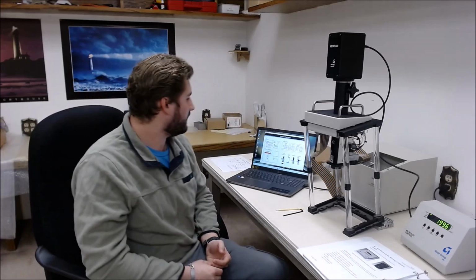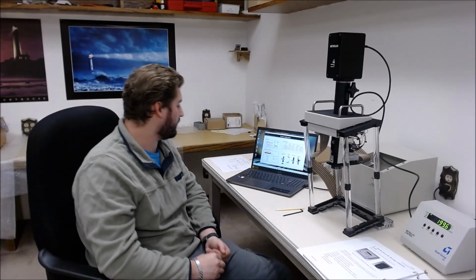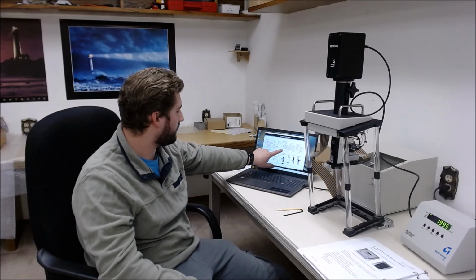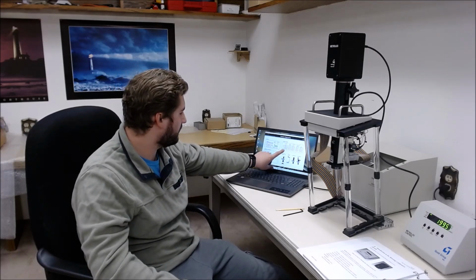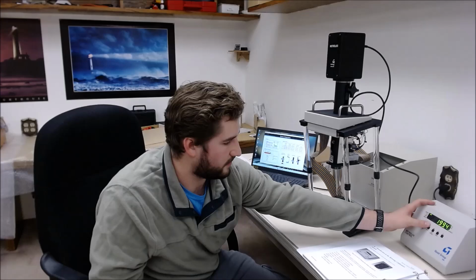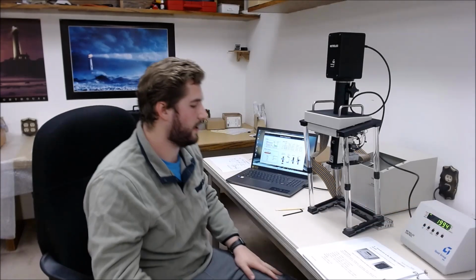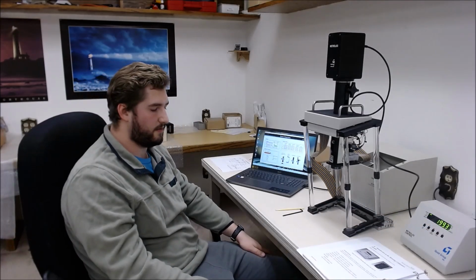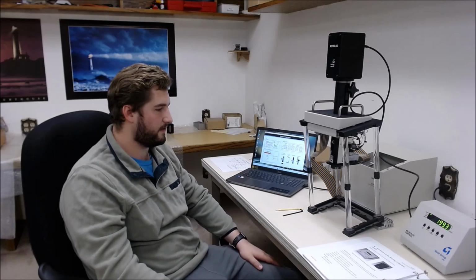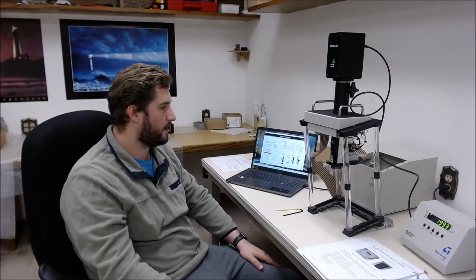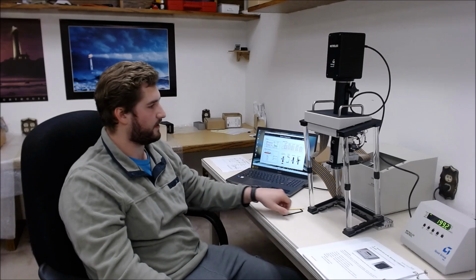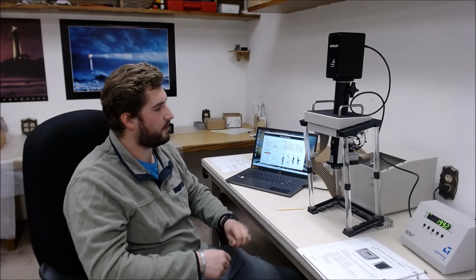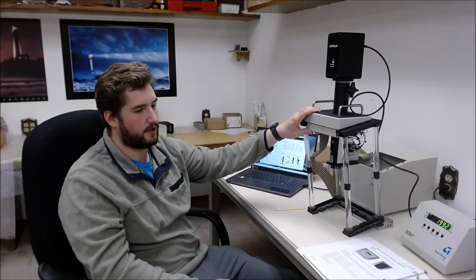Once both of these are stabilized, we will compare the values from the system diagnostics and the Metrolog controller value. If they are within 0.08%, the system is calibrated. If not, we will have to open up the bottom of the breaking point platform and adjust one of the pots.